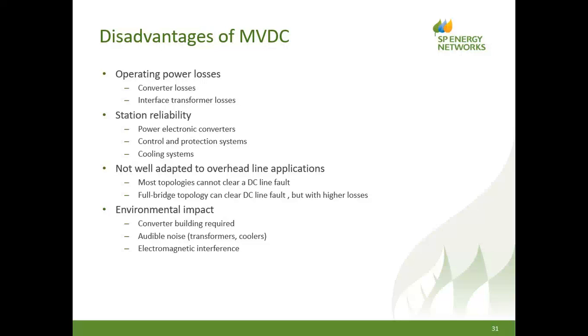And we must be conscious of the environmental impact of putting an MVDC link into both Anglesey and the mainland. We need a building. Kevin's mentioned that height could be an issue for the building in a primarily agricultural or domestic landscape. We have to be conscious of audible noise. The transformers will bring additional noise sources. The cooler fans will bring additional noise sources to the two stations. These will have to meet local planning regulations.